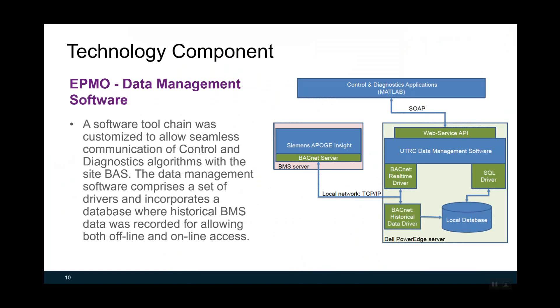Another component of EPMO is the data management software. A software tool chain was customized to allow seamless communication of the controls and diagnostics with the site building automation system. The data management software comprises a set of drivers and incorporates a database where historical BMS data are recorded, so we can do both offline and online analysis of data.